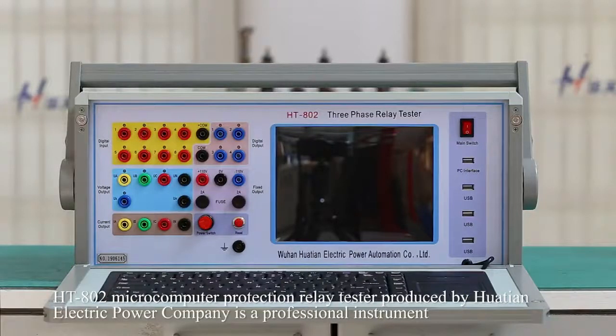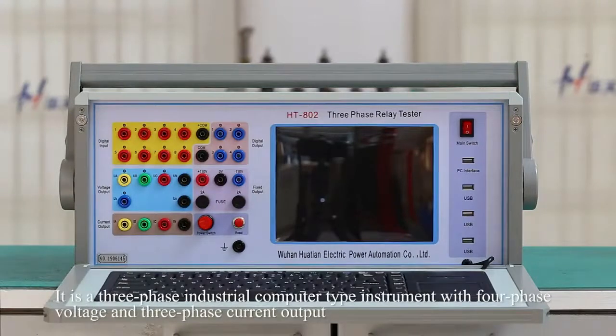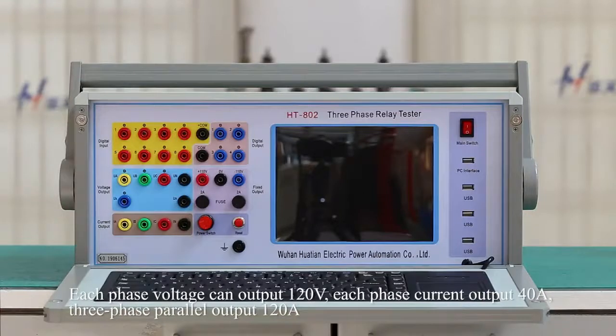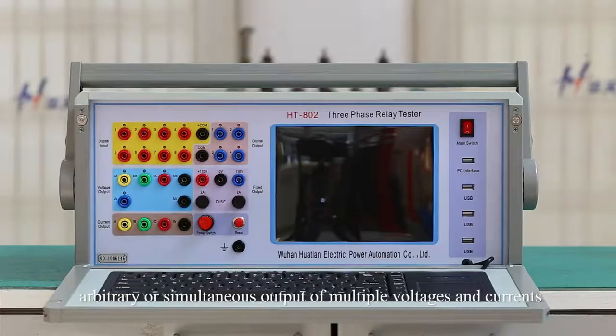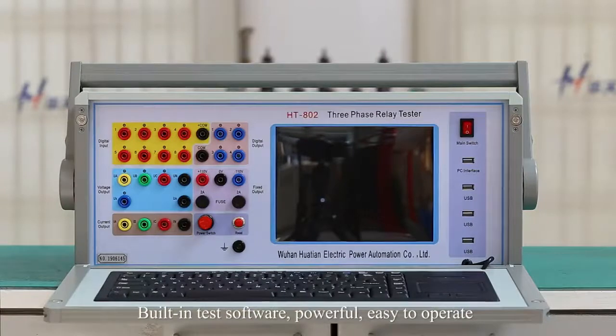HT802 Protection Relay Test Set, produced by Huatian Electric Power Company, is a professional instrument. It is a three-phase industrial computer-type instrument with four-phase voltage and three-phase current output. Each phase voltage can output 120 V. Each phase current can output 40 A. Three-phase parallel output is 120 A. It allows arbitrary or simultaneous output of multiple voltages and currents. It has built-in test software that is powerful and easy to operate.